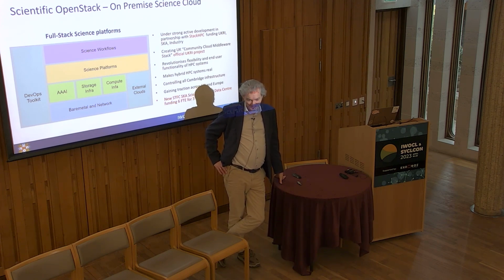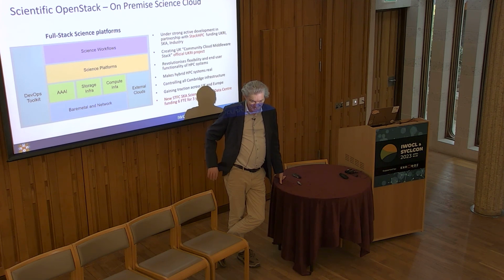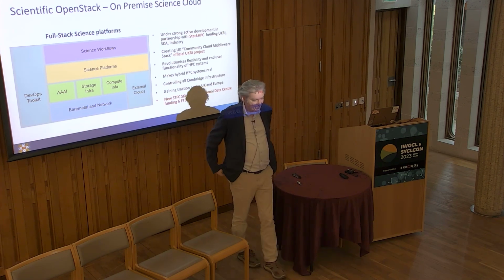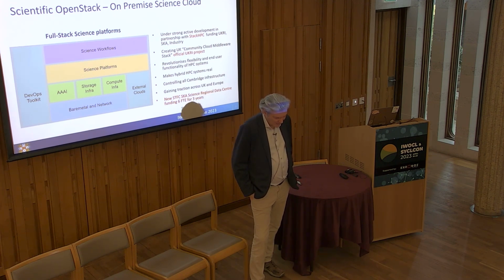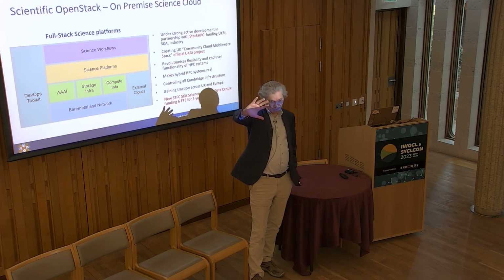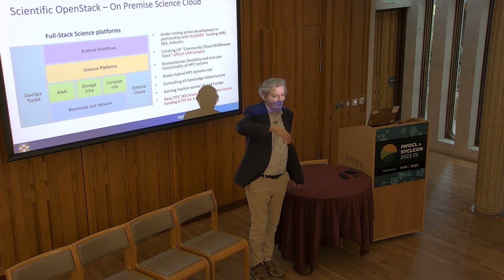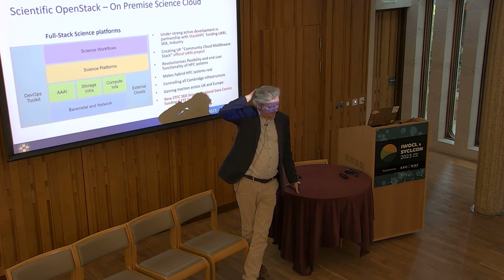There's a question at the front as well. Have you considered using an intelligent power allocator to target, say, temperatures and scale the frequency accordingly to target a temperature, which would allow you to reduce costs? Temperature is not really the thing. As I said, my cooling is only 7%. We need to keep temperatures within operational limits, but the temperature itself is not a driver of cost. We actually run the data center hot. We have very high ceilings, hot air goes up, cold air comes down. And so we run the data center as hot as we can within ASHRAE. So temperature is not really a thing. That metric does not correlate to cost. So we don't do it now.